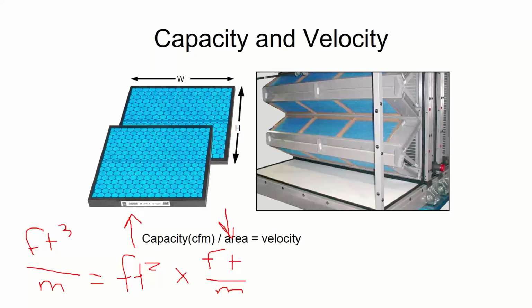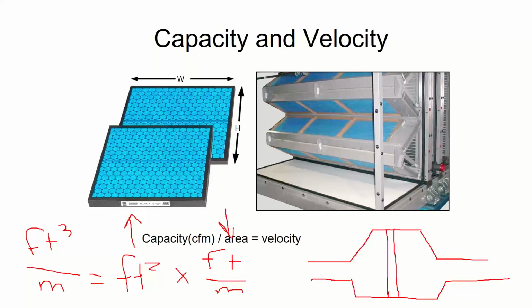I'd love for your duct system to come into the mechanical room like this, go to some really large, wide section of duct where my filter's at, to slow down the velocity pressure. But you're not going to give me a 20-foot tall mechanical room. That's just not going to happen. So instead, we put the filter in this V-bank fashion, because if you were to stretch that V-bank out, it would be like I had a big tall section temporarily. So as the air goes through that filter section, it has a slower velocity just for that little moment of time. And that's what I need to happen.